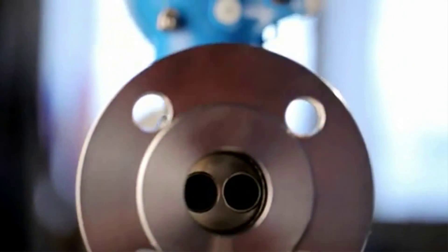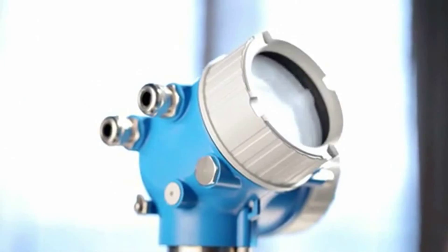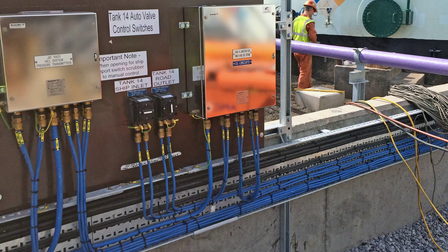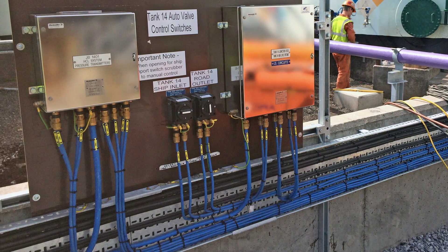Utilising the Class 1 vacuum pressure leak detection equipment means that future downtime for internal weld seam, floor and wall inspections is minimised, as the tank lining vacuum is digitally monitored for any vacuum loss fluctuations 24-7. The six vacuum instruments were connected to the client's on-site control system to alarm if any monitored zone failed due to an external or internal breach of the double skin liner.